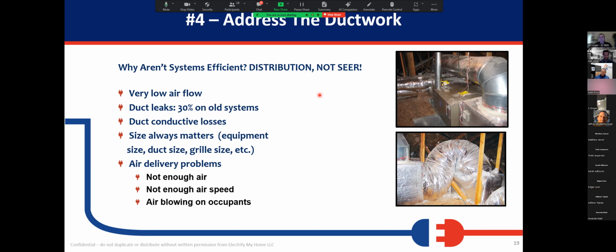Most of the time, the guys out in the field are not checking static pressure. They're not looking for things like thermal bypasses, or what can be a poorly executed sound loop, or whatever the reason for something like this would be. But distribution systems are the biggest robber of energy in the whole system. And if we take a box out and pop a new box in and don't pay attention to this, all those efficiencies we talk to our customer about are going to be worse.